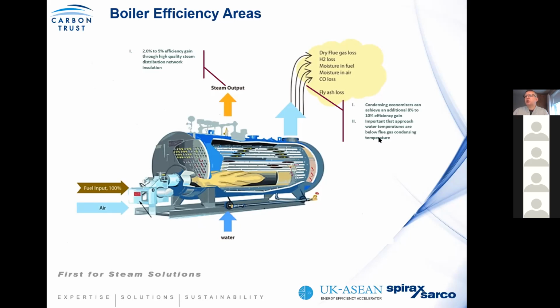However, it should be understood, especially for the likes of natural gas, that the condensates generated on the flue gas side are acidic. Because of the sulfur content in certain fuels, for example, and the carbon content, you get carbon dioxide gases, which create carbonic acid. And if there's any sulfur content, you create sulfuric acid. So the choice of materials means it's expensive. You're using stainless steel grade heat exchangers, but if you have quite a large steam demand, it can be financially attractive.